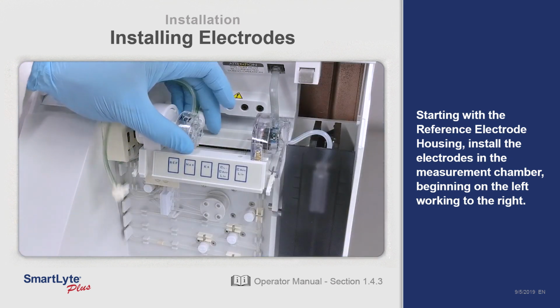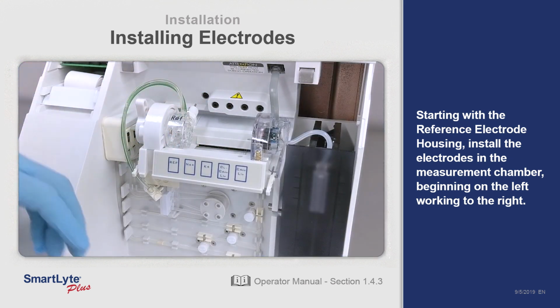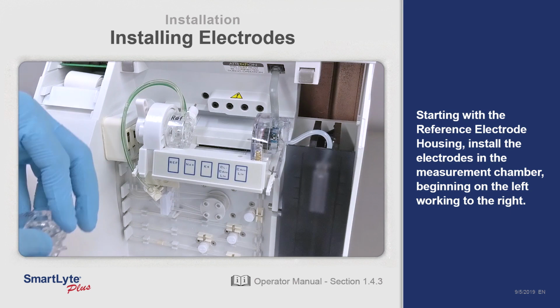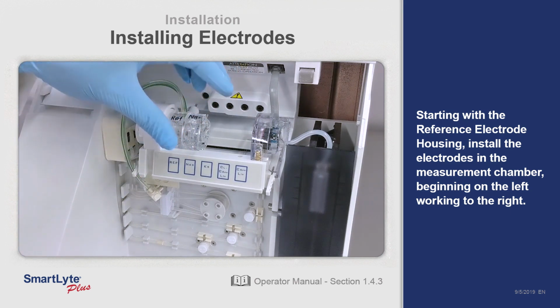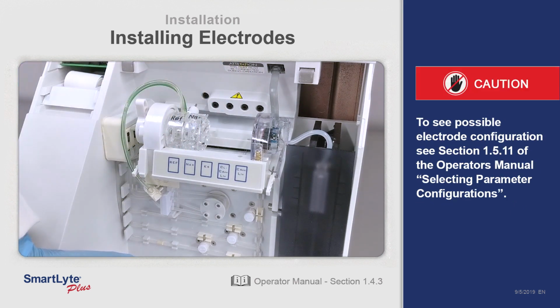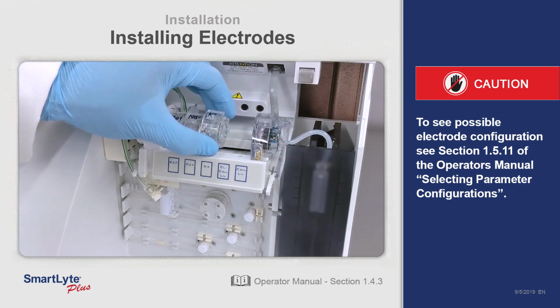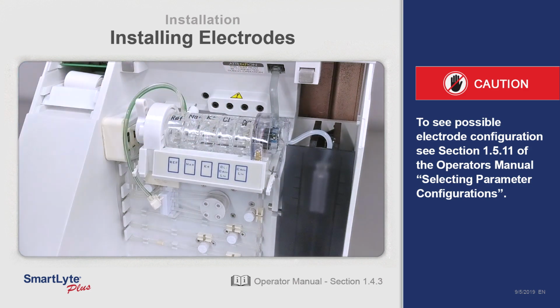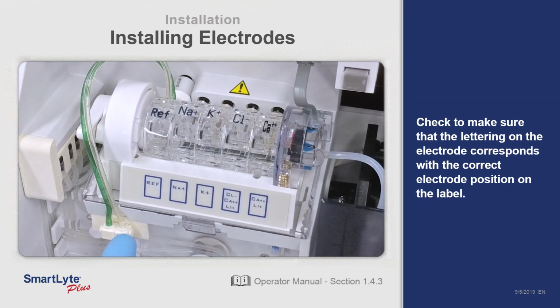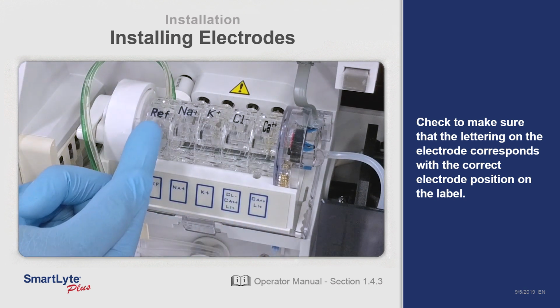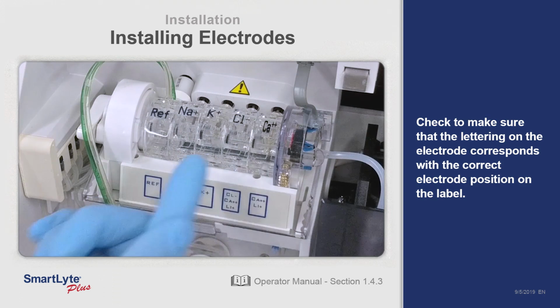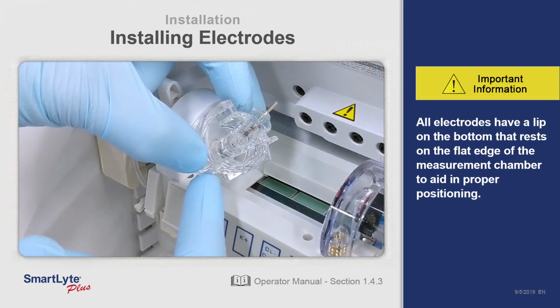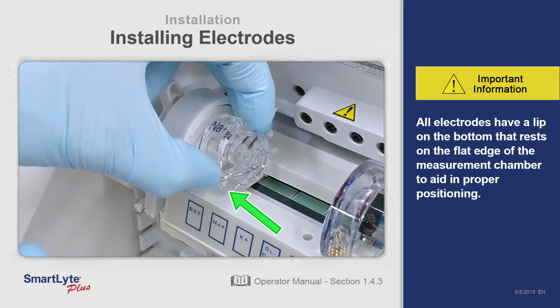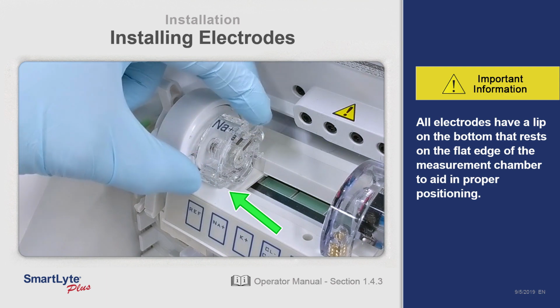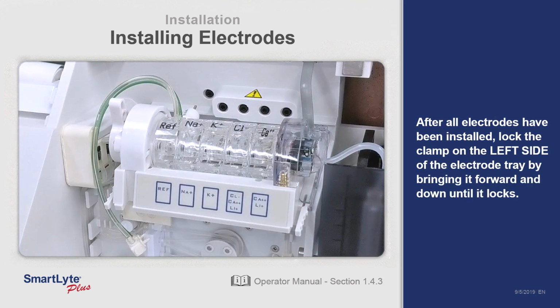Now install the electrodes in the measurement chamber, beginning on the left, working to the right. The reference electrode housing is installed first. To see possible electrode configurations, see Section 7 of the operator manual, selecting parameter configurations. Check to make sure that the lettering on the electrode corresponds with the correct electrode position on the label. Also, note that all electrodes have a lip on the bottom that rests on the flat edge of the measurement chamber to aid in proper positioning.